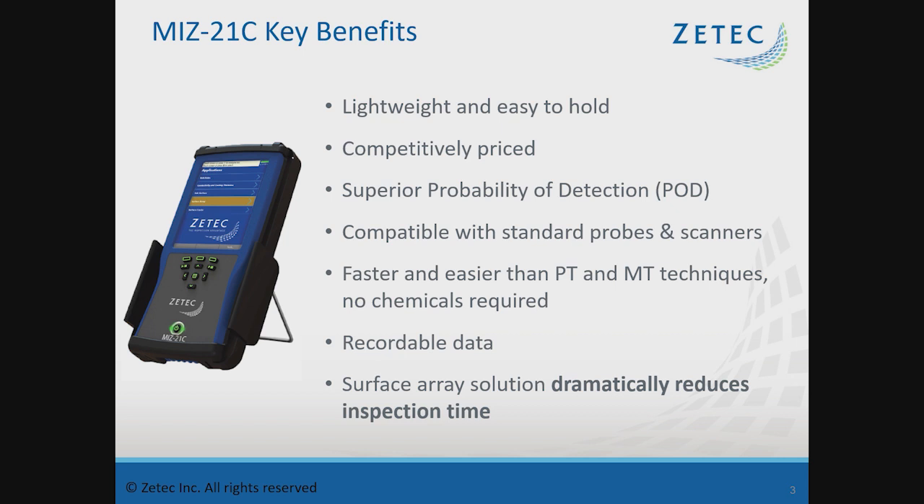Some of the key benefits are that it's very lightweight and easy to hold — about two pounds — and it's competitively priced. It has very high probability of detection. The acquisition boards have developed over time from previous MIZ instruments, carrying forward high performance for signal-to-noise ratio. It's much faster and easier than PT and MT techniques without dealing with chemicals. With array, you really start to see the savings against dye penetrant and magnetic particle testing. You can record and save data files for a part record of inspection, and the surface array dramatically reduces inspection time compared to standard eddy current.